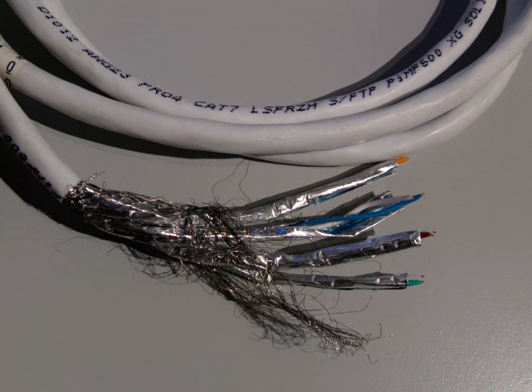Annex E, Acronyms for balanced cables, provides a system to specify the exact construction for both unshielded and shielded balanced twisted pair cables. It uses three letters: U for unshielded, S for braided shielding, and F for foil shielding, to form a two-part abbreviation in the form of XX/XTP, where the first part specifies the type of overall cable shielding and the second part specifies shielding for individual cable elements.